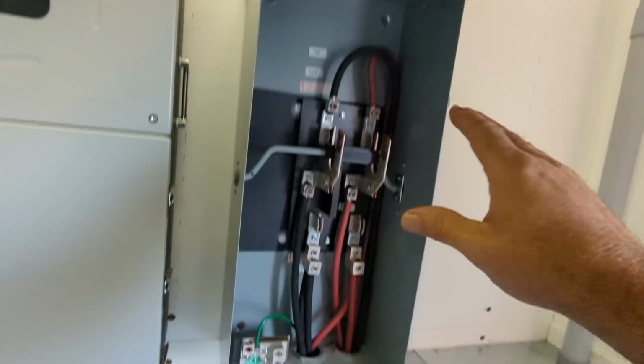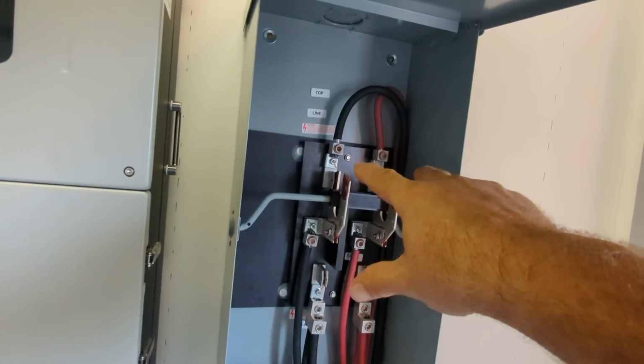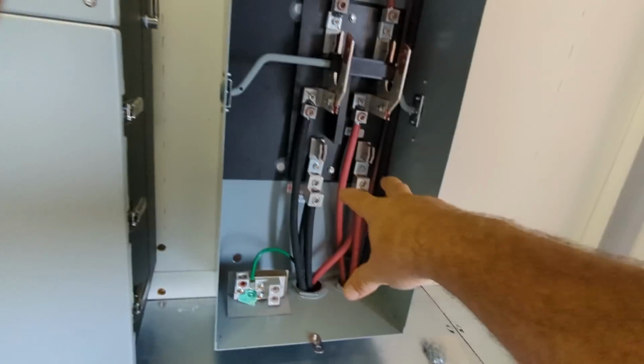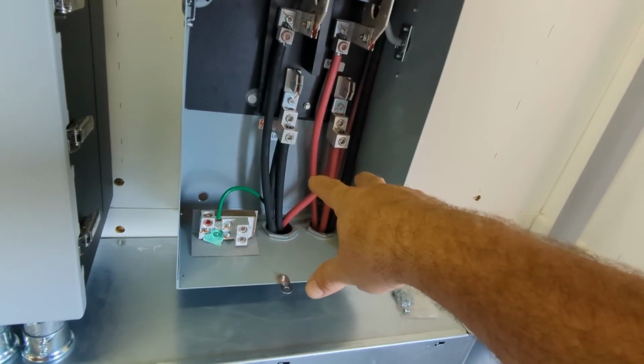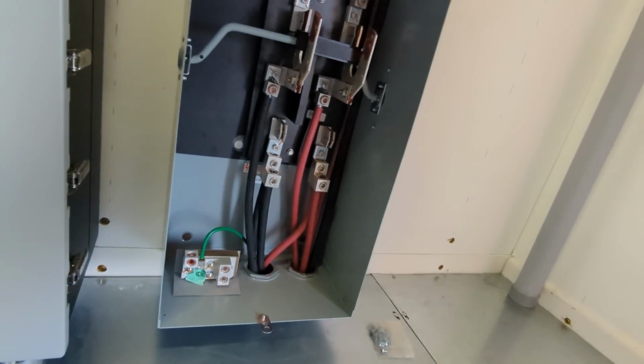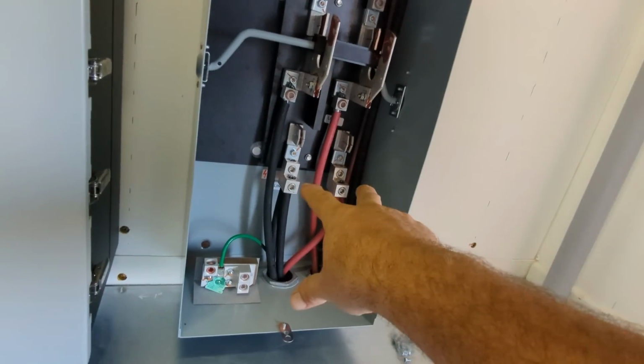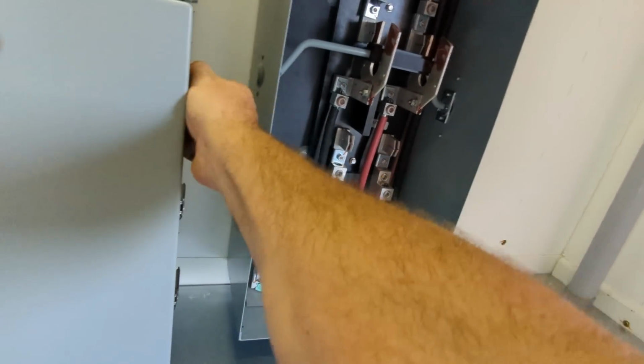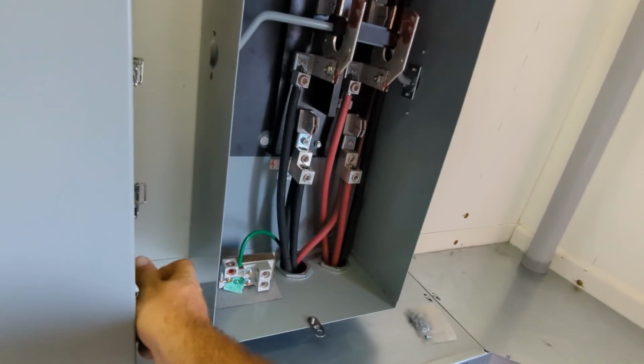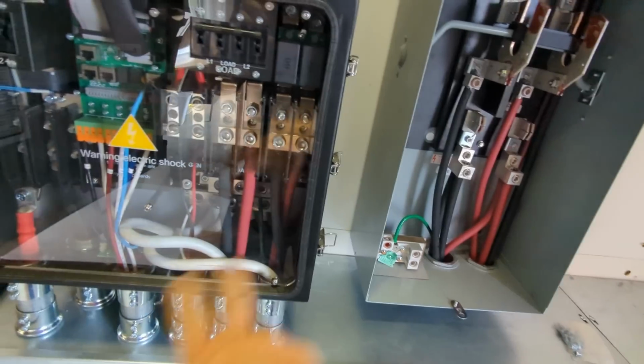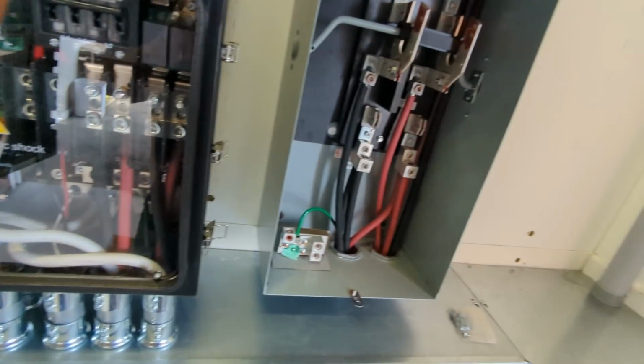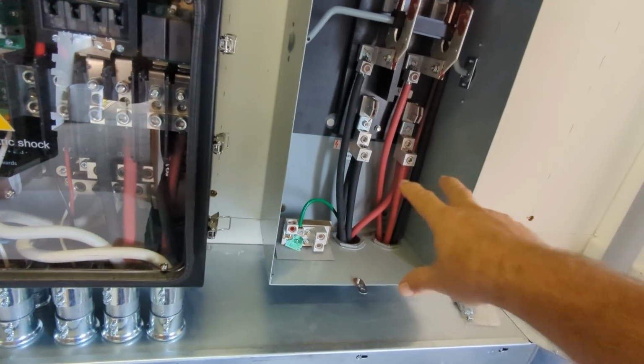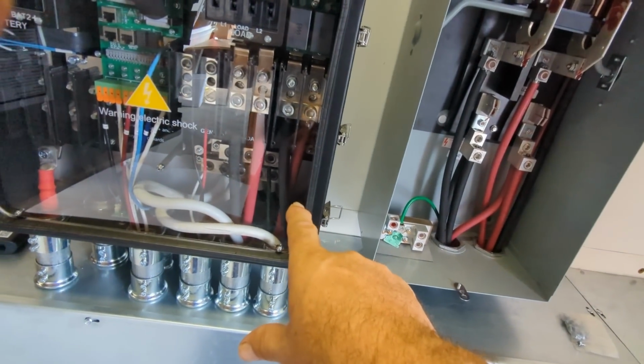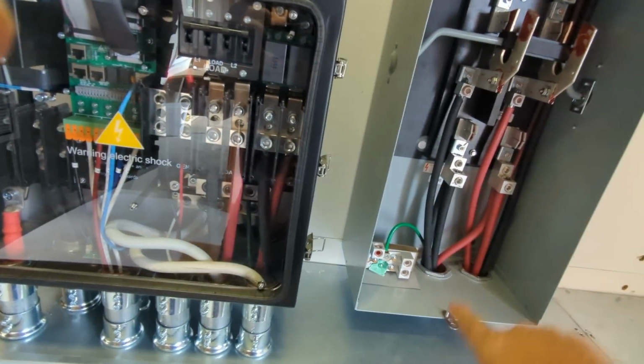For our bypass, we have the Sol-Ark on top and the grid on the bottom, and you see how we double lug the grid. So we bring the grid in, it goes from the meter to the disconnect to the bypass, and then from the bypass, it comes in and lands on the grid input. So the flow of power goes from the meter to the disconnect to the bypass to the inverter. Then out of the inverter, we hit the top.